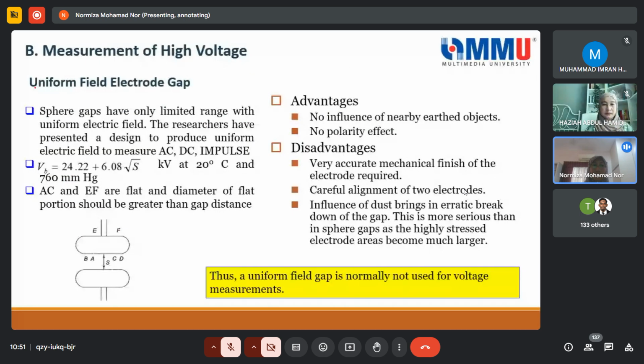So another type is a uniform field electrode gap. I have to say that actually uniform field electrode gap is not widely used in high voltage equipment or high voltage labs. This is more towards the research lab. But anyway, we will just see this simple construction here, that the sphere gaps have only a limited range with a uniform electric field, and the researchers have presented a design to produce a uniform electric field to measure AC, DC, and impulse. For example, VB here is how we calculate the breakdown voltage.